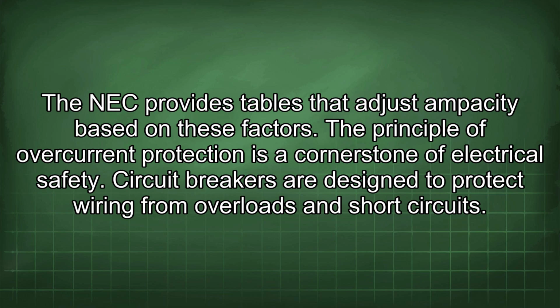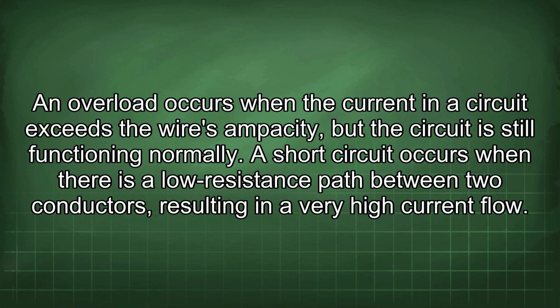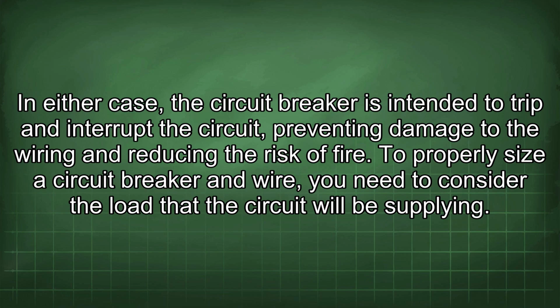The principle of overcurrent protection is a cornerstone of electrical safety. Circuit breakers are designed to protect wiring from overloads and short circuits. An overload occurs when the current in a circuit exceeds the wire's ampacity, but the circuit is still functioning normally. A short circuit occurs when there is a low resistance path between two conductors, resulting in a very high current flow. In either case, the circuit breaker is intended to trip and interrupt the circuit, preventing damage to the wiring and reducing the risk of fire.